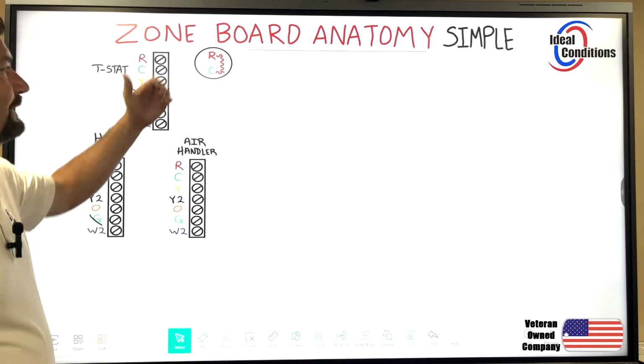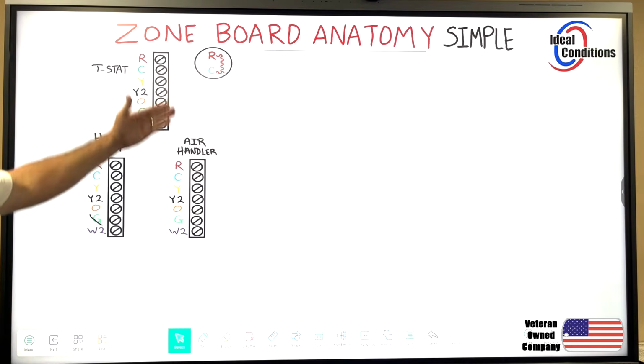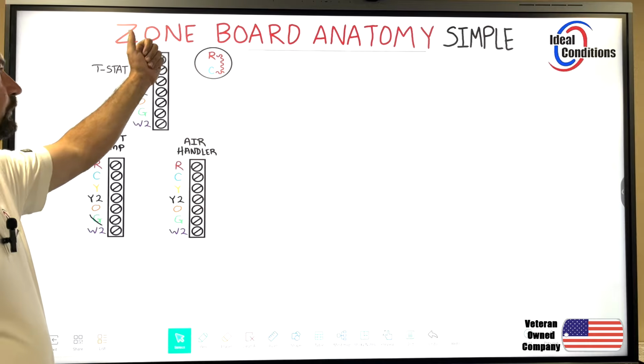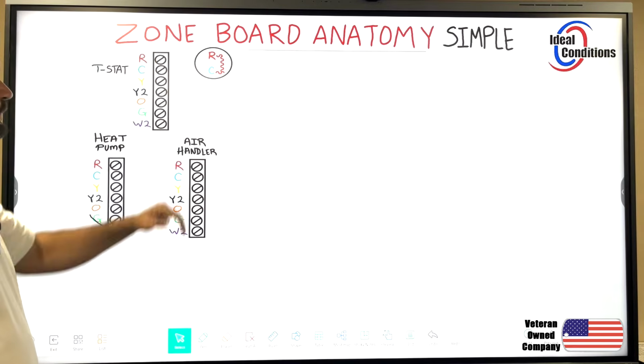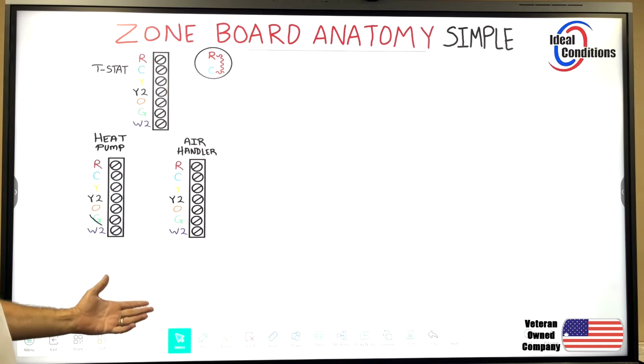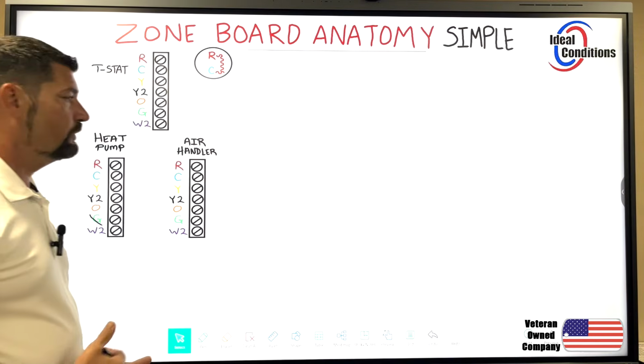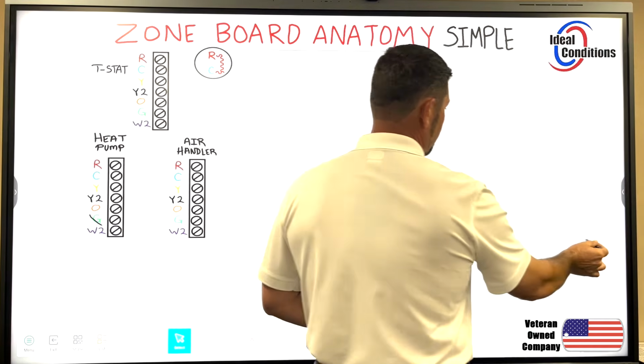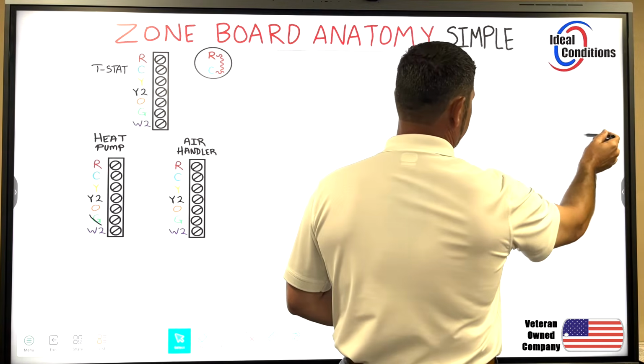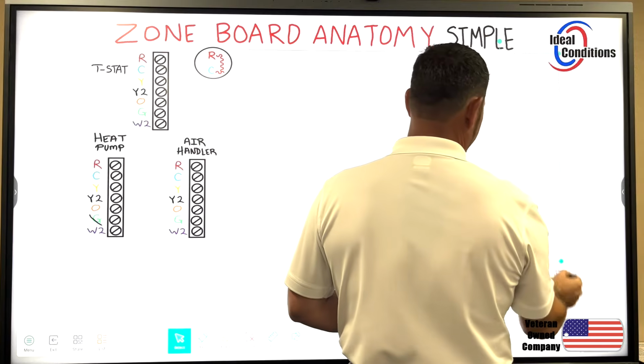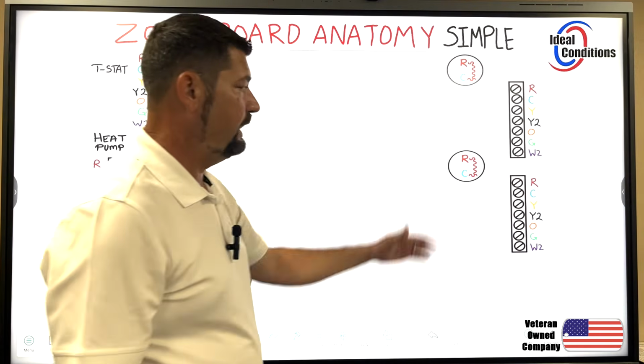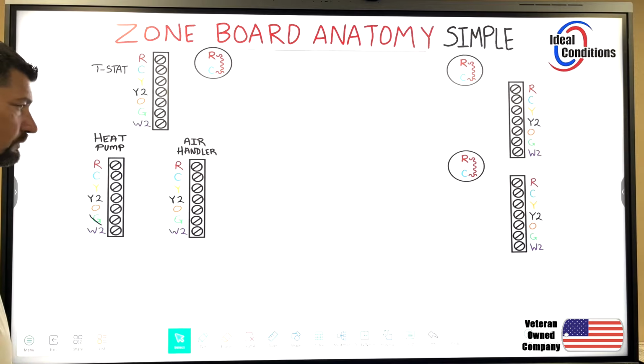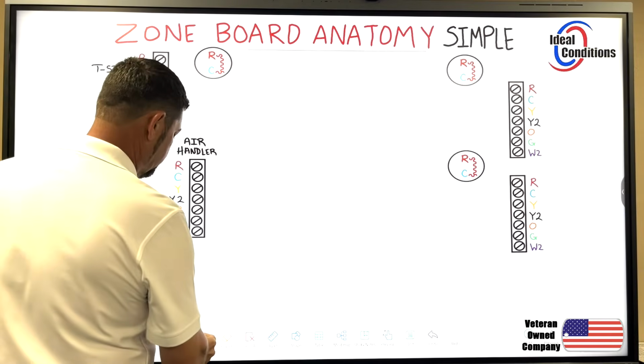So this would represent a damper. It's just a 2-wire damper. Once we energize it, this damper will close. If it's not energized, the damper will stay in the open position. And so if I wanted to have another thermostat, then what I'm going to have to do is have a zone board basically. So I'm going to go ahead and add 2 more thermostats. And let's try to do this without a zone board. Let's just see how crazy that's going to look. We're going to wire this again.